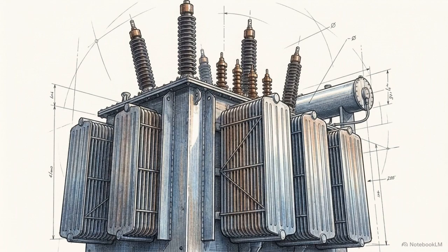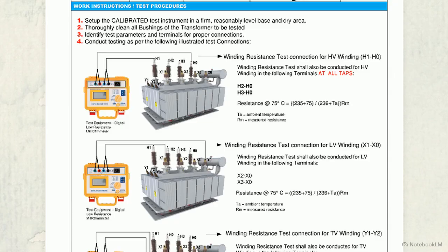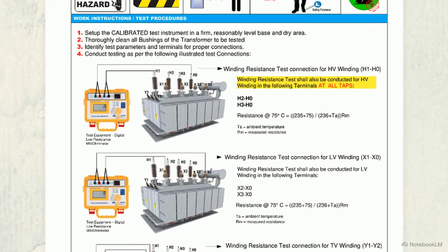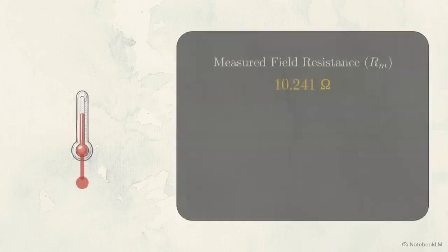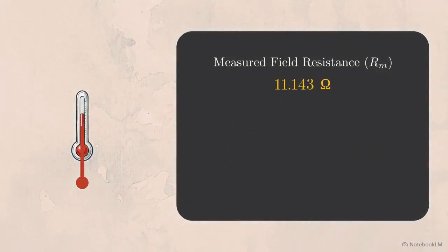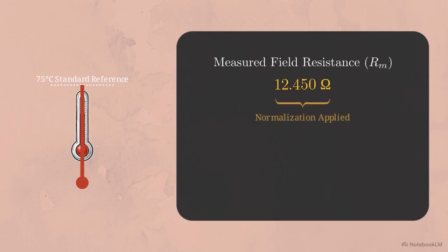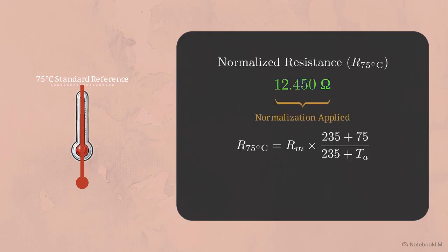Moving inside the tank, this schematic outlines winding resistance testing. We use Kelvin leads on primary and secondary connections to eliminate test lead resistance errors, recording measurements across all sequential tap changer positions. Because copper and aluminum resistance changes with heat, we apply a specific temperature correction formula, normalizing all field readings to a standard reference of 75 degrees Celsius for accurate factory comparison.